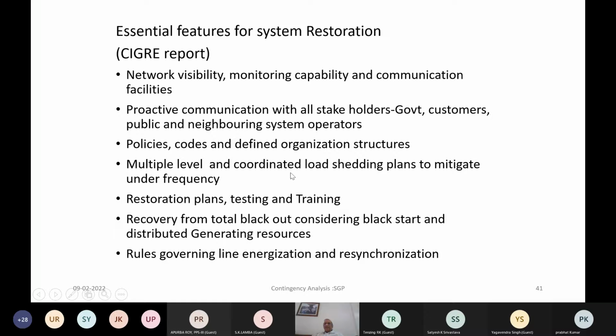Multiple level and coordinated load shedding plans to mitigate the under frequency condition is a must. Restoration plans, periodic testing and training of the people. Recovery from total blackout, considering the black start facility, and also considering the distributed generating resources. Rules governing line energization and resynchronization. Post blackout, one of the important restoration processes is how you synchronize back with the rest of the grid.